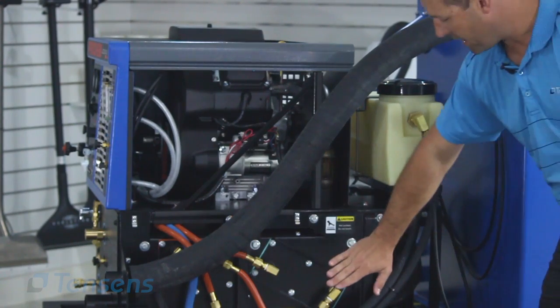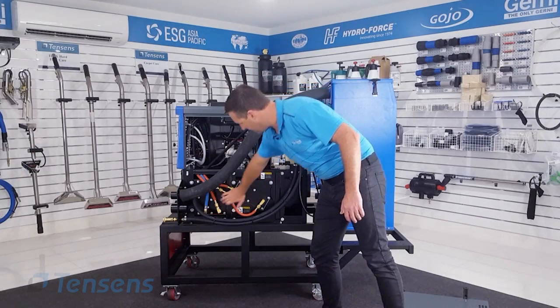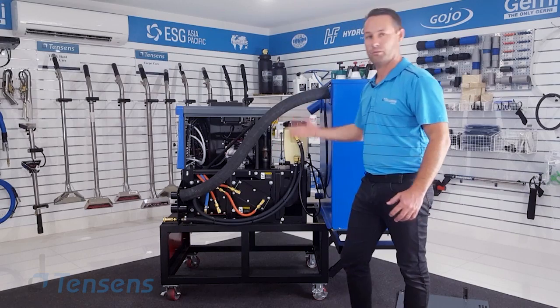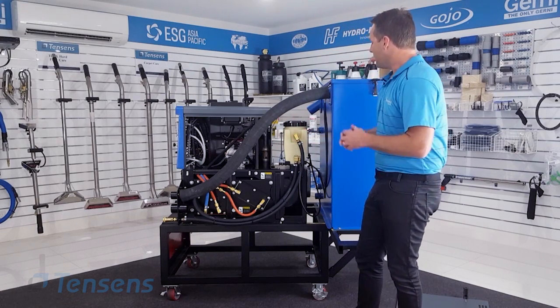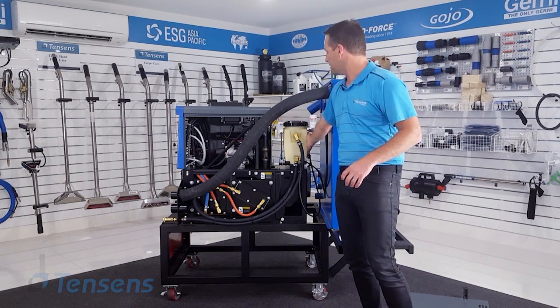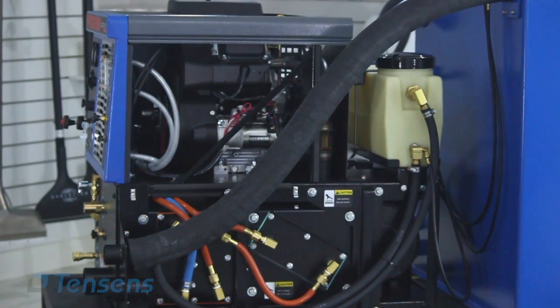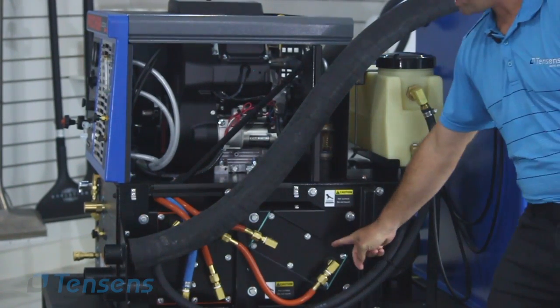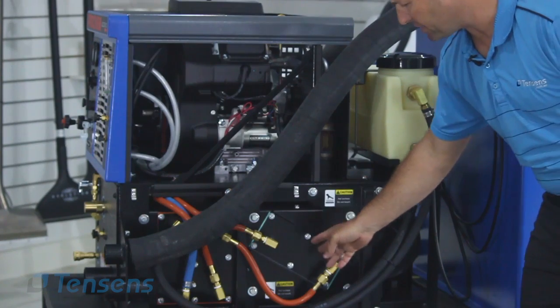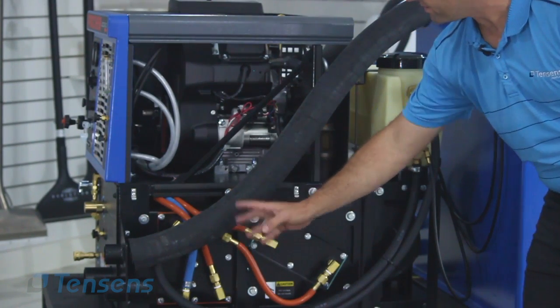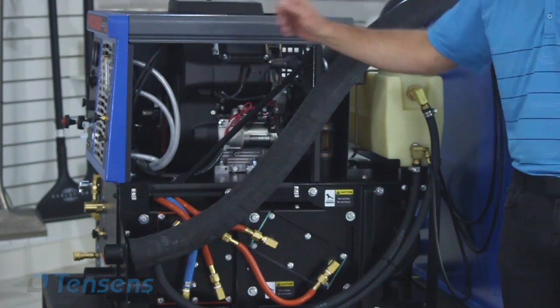The heat exchange down here. So we've got 3 heat exchangers, as I mentioned before, 2 stainless and 1 copper. So the way the system works is you have clean cold water inside here. It goes into your pressure pump. From your pressure pump, it goes into the first heat exchange. From the first heat exchange, it goes into the second heat exchange. From the second heat exchange, it goes through to your solution manifold.